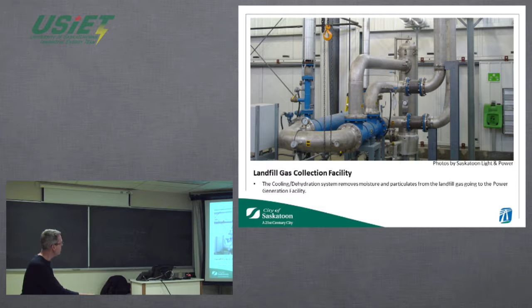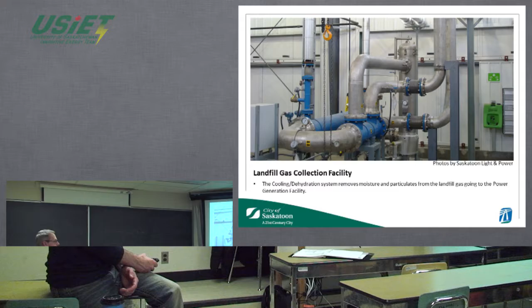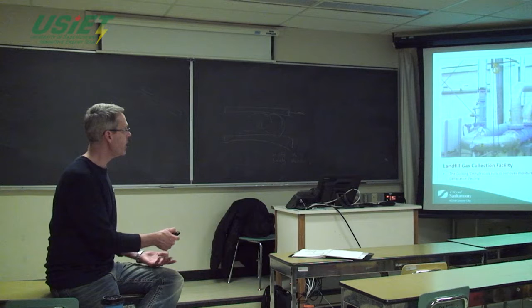This is a cooler dehydrator. And so after the gas comes out of that compressor, whenever you compress gas, it heats it up. And so we have to cool that gas. And we also have to cool the gas to knock the moisture out of it. So we cool it, and then this chiller, which is the blue light in here, cools it down to a dew point of about 4 degrees Celsius. And that should knock out the rest of the moisture. And then we have what's called a coalescing filter to remove any particulate matter that's still in the gas at that point. So when it comes out of this, it's clean, dry landfill gas. We don't remove any H2S or CO2 or nitrogen from the gas. Obviously they're CO2 or nitrogen or inert gases, but you can still burn the methane even with them in the mix.